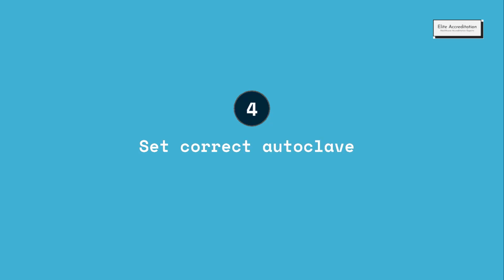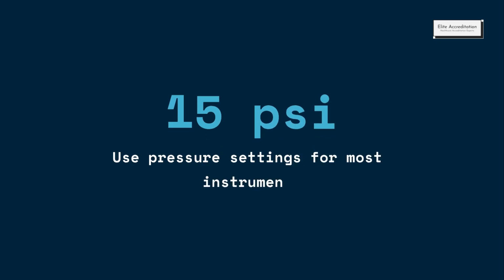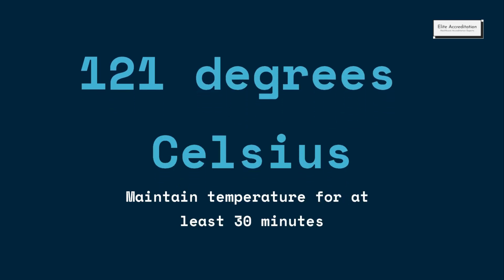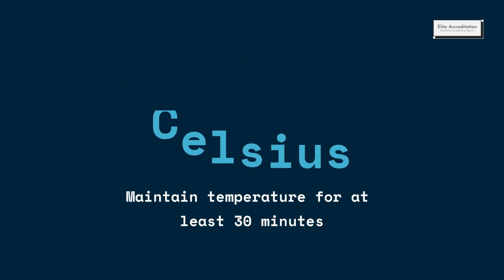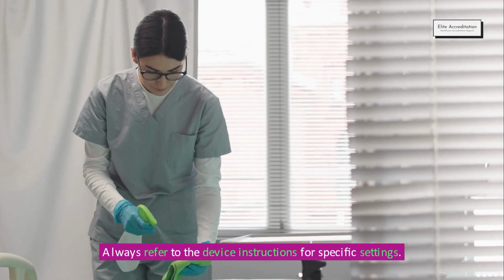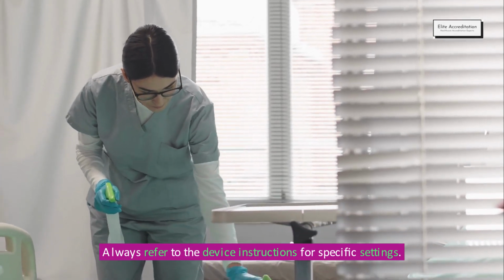Now, set the correct parameters on your autoclave. For most instruments, use a pressure of 15 psi. Maintain a temperature of around 121 degrees Celsius for at least 30 minutes. Always refer to the device instructions for specific settings.